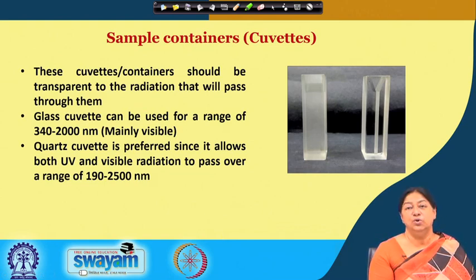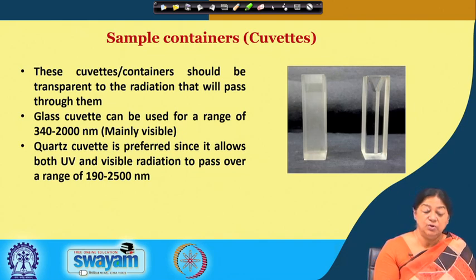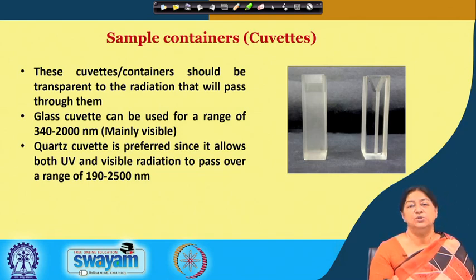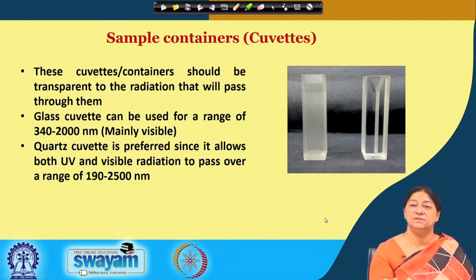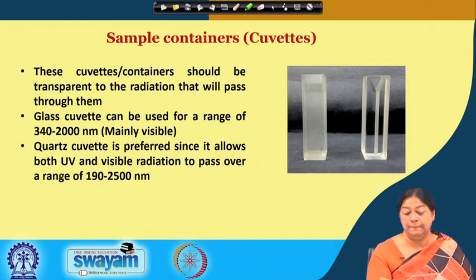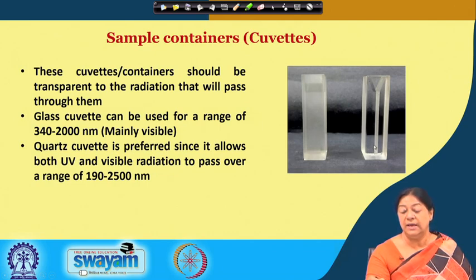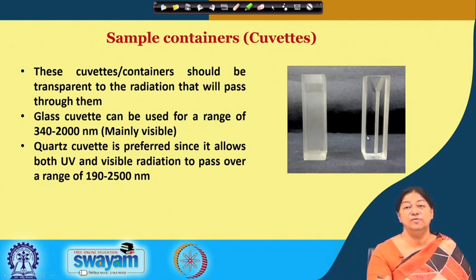The sample containers are called cuvettes. We need transparent cuvettes — glass or quartz cuvettes — which have minimum absorption of light, because we do not want the sample cell holder to absorb any light; only our sample should absorb the light. There are specific cuvettes with extremely narrow bore for when we have a lower volume of solution. Different volume cuvettes can be purchased for the equipment, and they are usually one centimeter by one centimeter, so the path length is one centimeter.